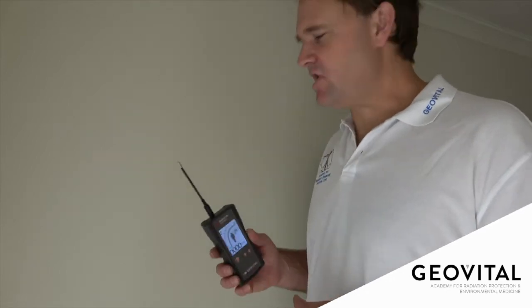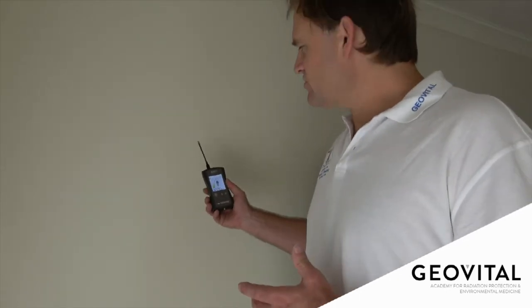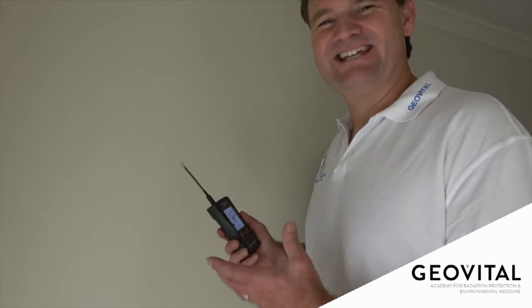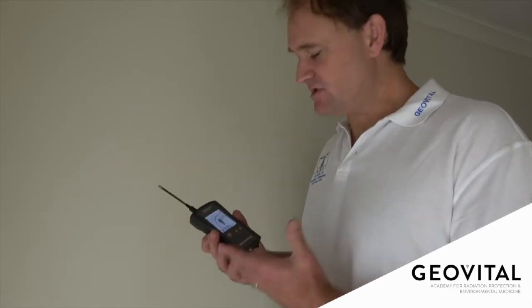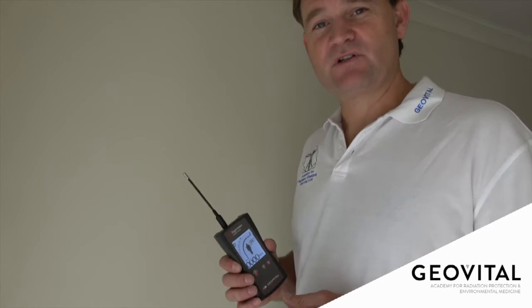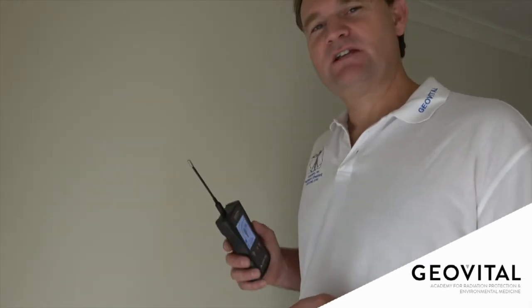If somebody's helping you take measurements, especially when circuits are turned off and you're having low readings, make sure that people don't rub the antenna against the wall. This could cause friction. It's a very sensitive instrument and that'll give you a spike in the reading. So just always try and hold it as still as you can.